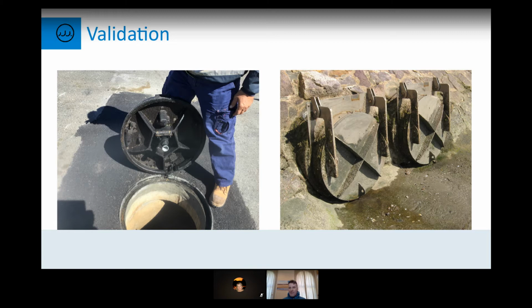The goal during installation should be to verify the complete install end to end. We want to prove that the sensor readings are correct, then send the data via the selected method to its end destination. It sounds simple, but often many of these steps are missed or incomplete, so only part of the installation is verified.